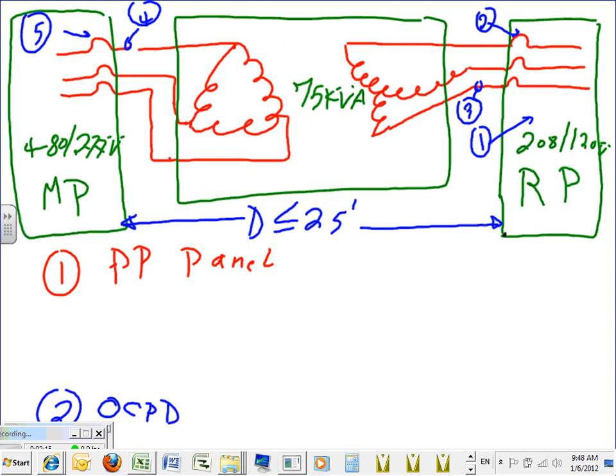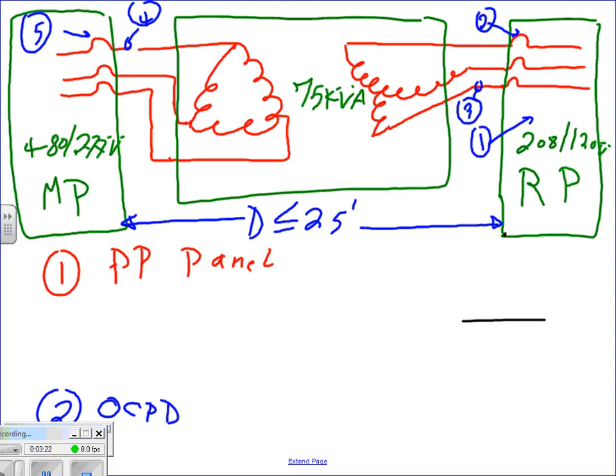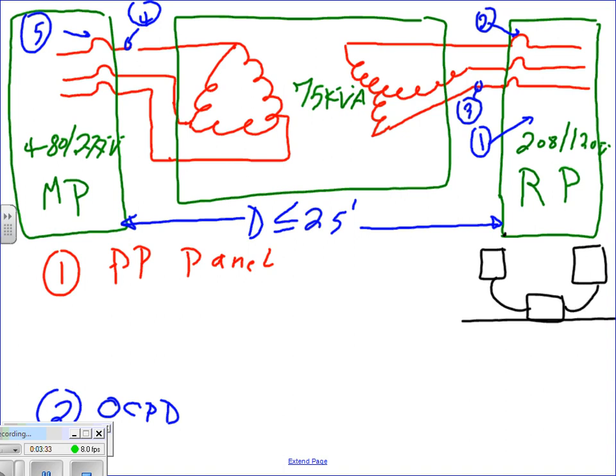If you want to do a riser for this, it would look like: a panel here, a transformer on the floor, and another panel here, with a cable going from the main panel to the transformer and from the transformer to the receptacle panel. The cable distance from the main panel through the transformer all the way to the receptacle panel is 25 feet or less - probably about 8 feet each leg, so it's not hard to achieve.